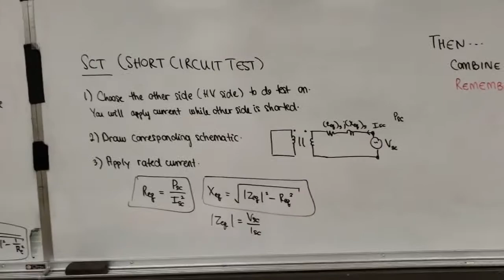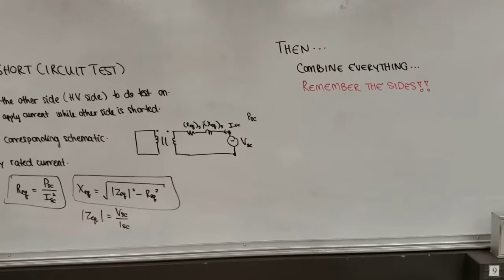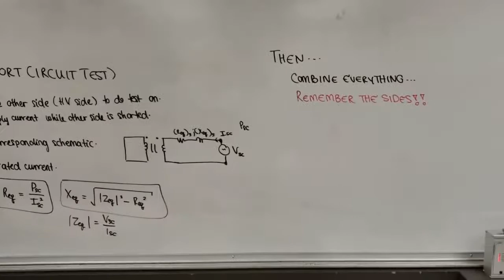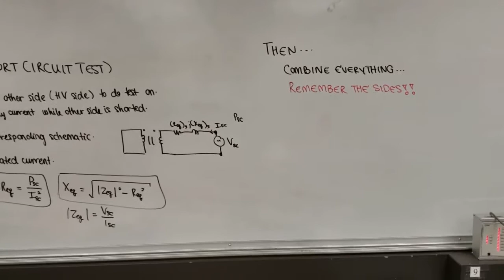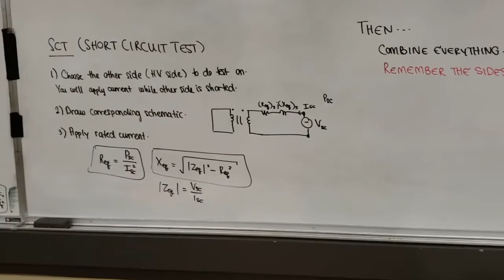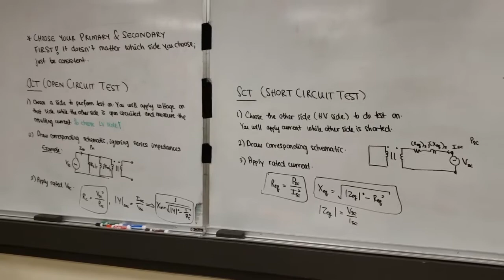Once you choose that side, as a huge thing to help prevent mistakes, draw your schematic right away for this test. If you chose the primary side, draw that circuit. The reason it's important to designate and be consistent about which side you're on is because at the end you want to combine all your impedances to one side and do the per unit conversion, and then we can tell if the transformer's specs are good or not.